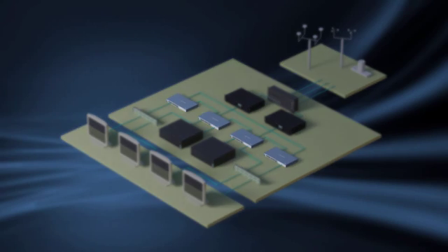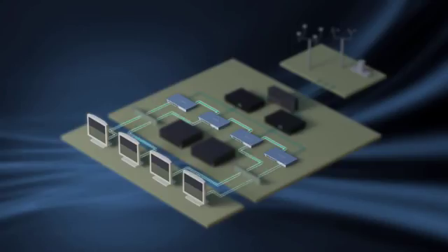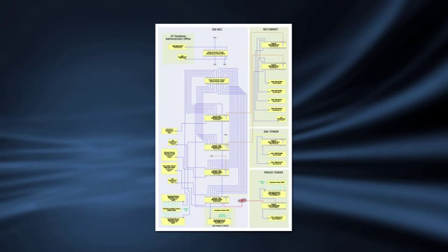Each NCC is equipped with 4 network switches connected in series or chained together. All workstations in a single location are never connected to a single network switch, helping prevent a complete outage if one of the network switches were to fail. For example, if the tower has 4 workstations, each one would be connected to a different switch in the control cabinet. If switch 2 fails, 3 workstations remain operational. A detailed network topology diagram will show you where all port connections should be made to create this failover protection.